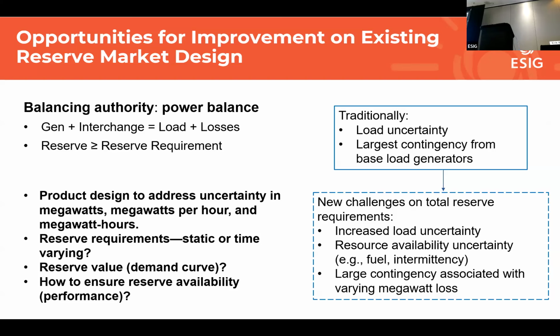In general, I think the reserve product design needs to be more dynamic instead of a static requirement. Traditionally, the contingency reserve covers the largest generation outage, but some of these audience members already asked what if the reduction of renewables can happen quickly and on a much bigger scale. I think this already happened at MISO: the wind forecast error, coupled with some load pickup, can cause a significant amount of ramping need in a very short time window.